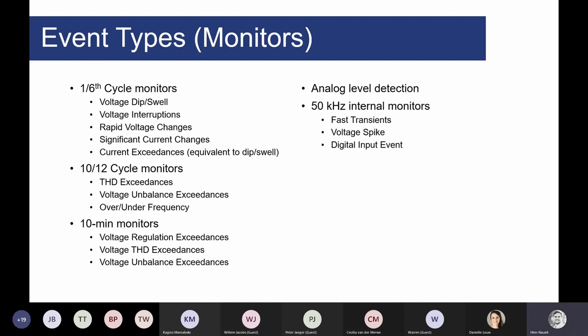Rather than recording the full waveform stream, we have event monitors that can be configured to record diagnostic data such as waveforms, the 1/6-cycle RMS and phasor, and 10-cycle or 12-cycle harmonic data.